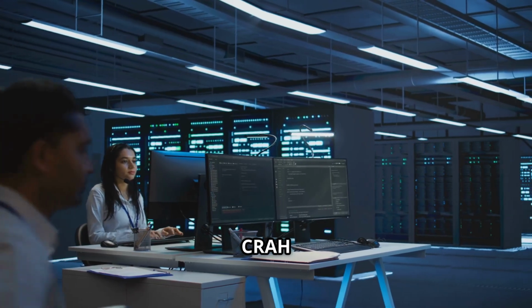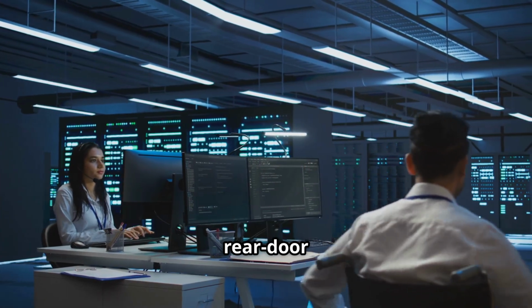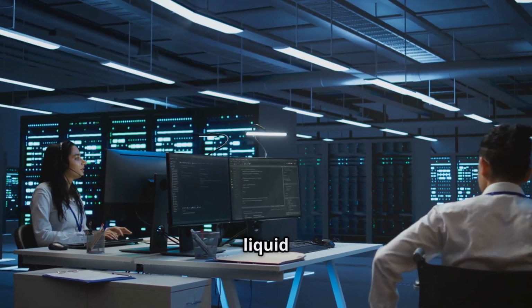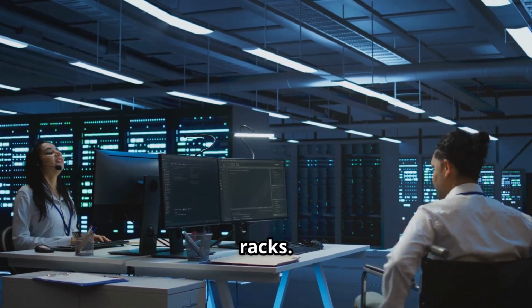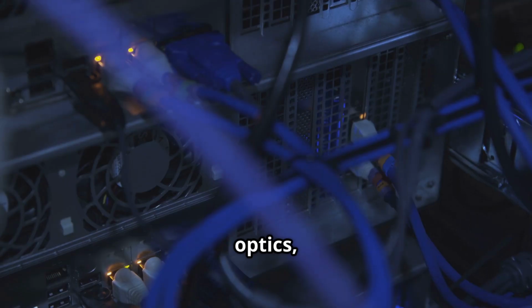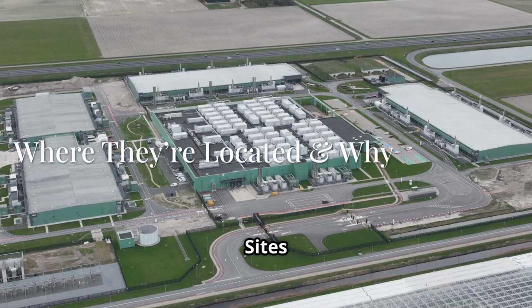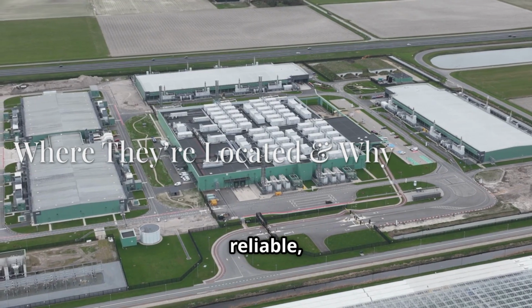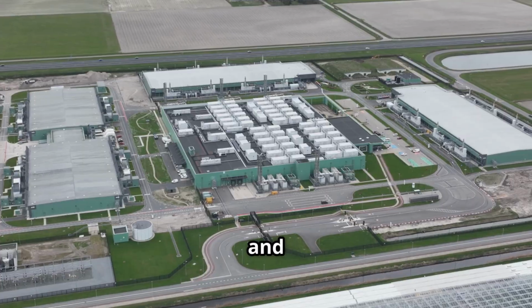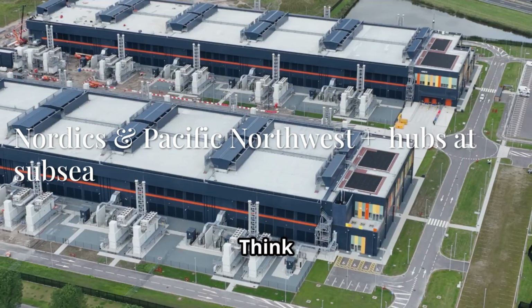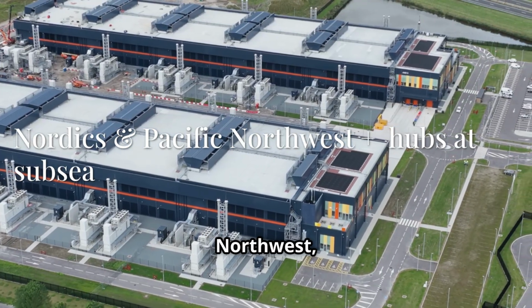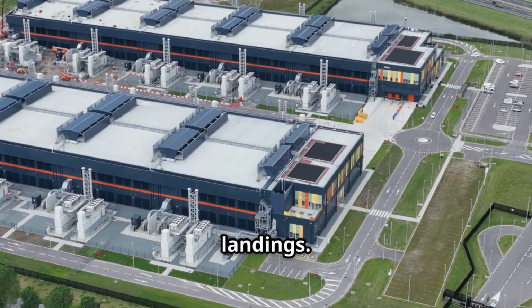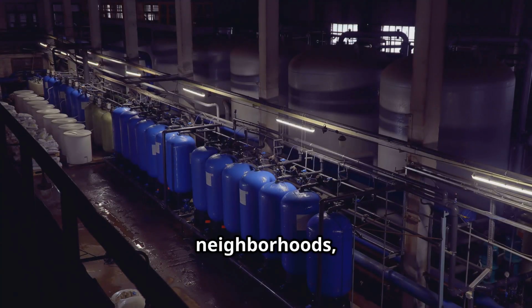Cooling uses CRAH and CRAC units, rear door heat exchangers, and direct-to-chip liquid for high-density racks. Networks use leaf-spine with optics, and multiple availability zones isolate failures. Sites cluster where power is cheap and reliable, climates are cool, and fiber converges—think Nordics and the Pacific Northwest, plus hubs near subsea cable landings. This enables waste heat reuse into neighborhoods, closed-loop seawater cooling, and evaporative systems in deserts.